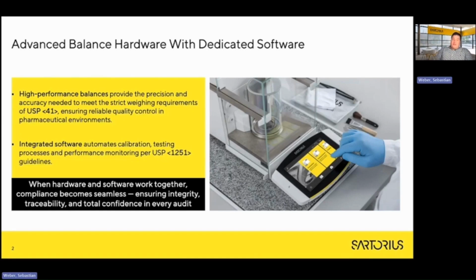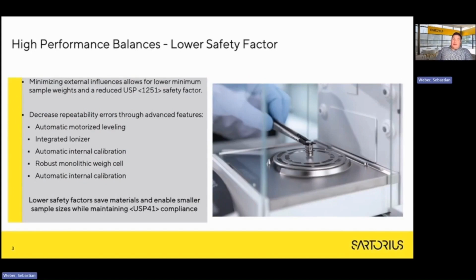When we start first talking about the high-performance balance hardware, we should talk about minimum weight and the safety factor. As Julian explained before, minimum weight is the smallest net sample you can weigh and still trust the result. The safety factor is the extra margin you add on top of the minimum weight to be safe. And a high-performance balance lets you use a lower safety factor because it's more stable and repeatable.